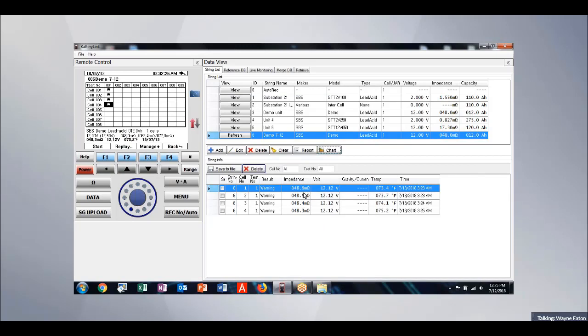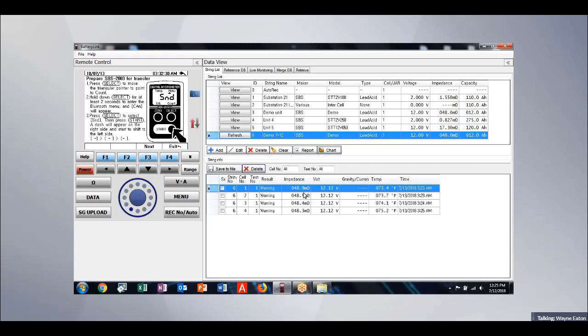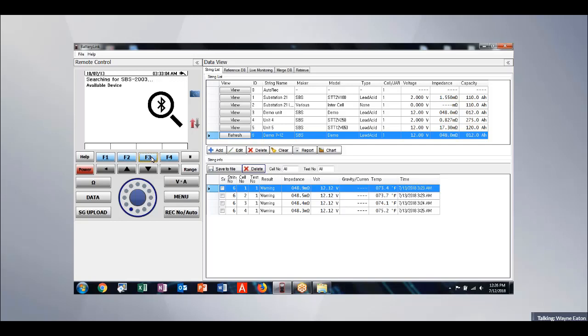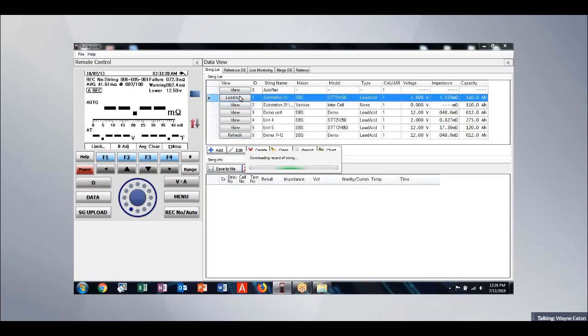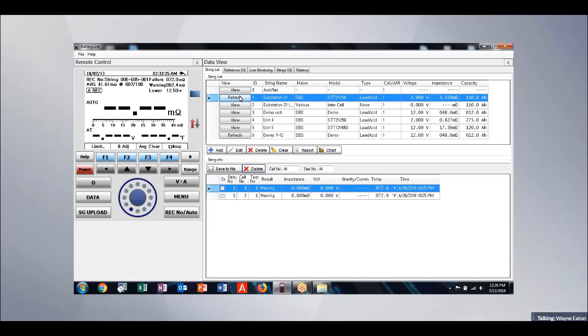So one of the features we integrated into the 6500 is the SBS-2003 digital hydrometer, and we built in a Bluetooth interface. So taking specific gravity readings, I'd go through the string, I'd take all my resistance readings and voltage readings with the 6500. I'd use the 2003 to take all my specific gravity readings. I'd press this upload button on the front of the SBS-6500. Follow the on-screen instructions for the 2003 to get it into the Bluetooth transmit mode, and then simply hit next in the software. And the SBS-6500 is automatically going to pair with the 2003, grab all those specific gravity readings, and then download them into the SBS-6500 and put in with the battery voltages and internal resistance values that I measured.